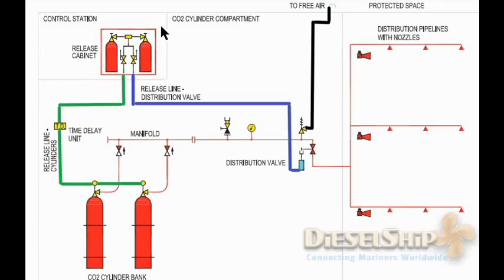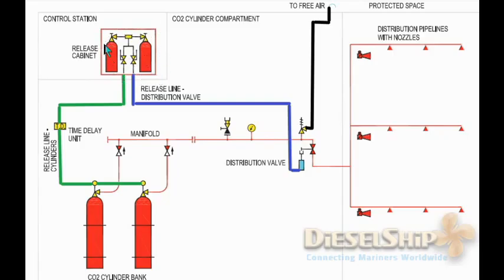Let's see what are the components inside the valve control station. This valve control station can be located at different places but definitely outside the space to be protected — here, the engine room. Otherwise you can't operate it in the event of fire. There are three main possibilities for its location: one is the fire control station, another is the CO2 room itself, and the third is just outside the engine room entrance.